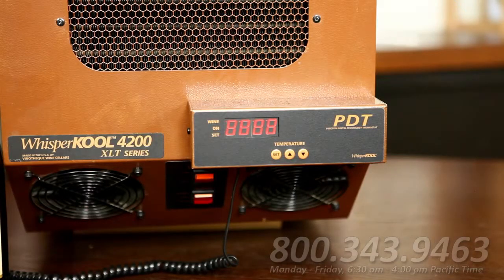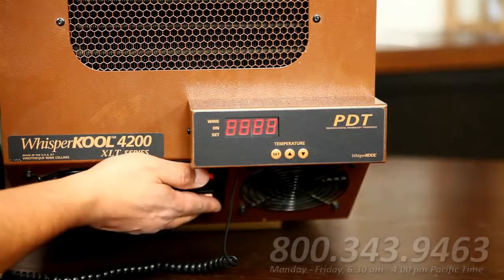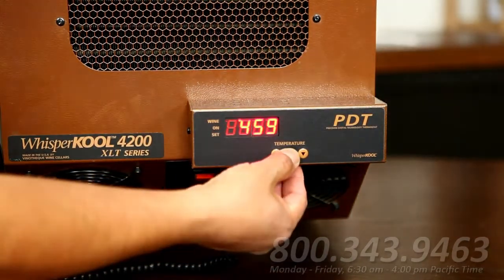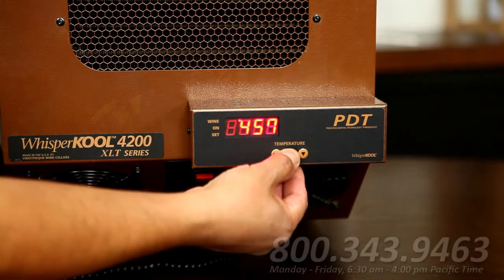There's also another way to test your thermostat. When you first turn it on, press and hold the up arrow. The PDT should show a 5-minute countdown to the unit turning on. If the display does not show the countdown, or if the unit does not turn on when the countdown finishes, the thermostat needs to be repaired or replaced.